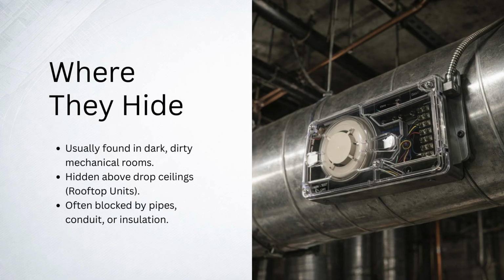The first challenge with these devices is simply finding them. Unlike a ceiling spot detector, duct detectors are often hidden in the darkest, dirtiest parts of the building. You will find them in mechanical rooms, high up in warehouse rafters, or hidden above drop ceilings servicing rooftop units. A major failure point I see is accessibility. If a detector is installed behind a wall of conduit or wrapped in insulation where you can't open the cover, it is impossible to service. And if you can't service it, it will eventually fail.